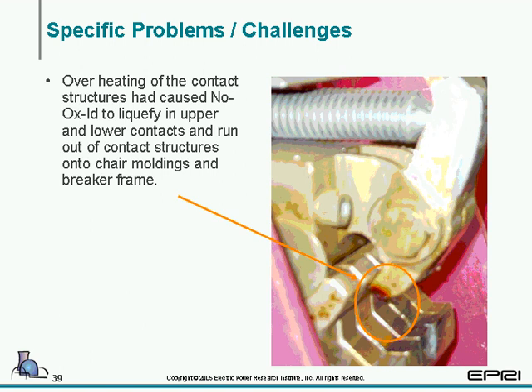Very first one to take a look at is lubrication. In this particular picture, you'll see where we have a yellow circle around an actual drip of lubricant, where it had dripped out of the contact structures and was dripping down onto the mains, where the contacts had received so much heat or built up so much heat that it caused the lubrication to actually liquefy and drip out.